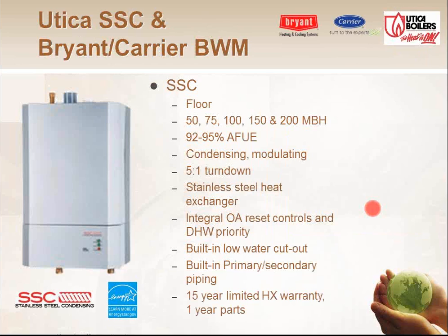So one of the other things that we can do with a low mass boiler, if we want to get away from that primary secondary piping change, right? On new construction, no big deal, or new install, no big deal. But if I'm doing a residential change out of an old cast iron boiler, maybe I don't want to put a second pump in and have to wire power to it and change the piping around. Maybe I just want to take one boiler out, put the other boiler in, and not have to do any extra electrical work there. That's where this SSC boiler comes in.